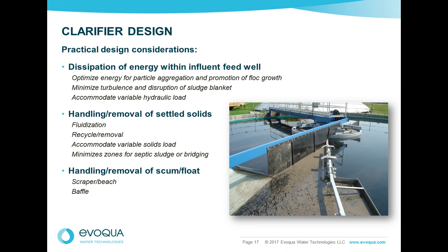Another consideration is the proper design to handle solids, to keep the floc bed fluidized and reliably remove them from the system, minimize bridging and formation of septic zones, and these factors in the solids handling. And also another consideration, because the settling process is imperfect and variable, is the proper design to remove and manage scum and float, which can sometimes accumulate on the surface of the clarifier under some conditions.